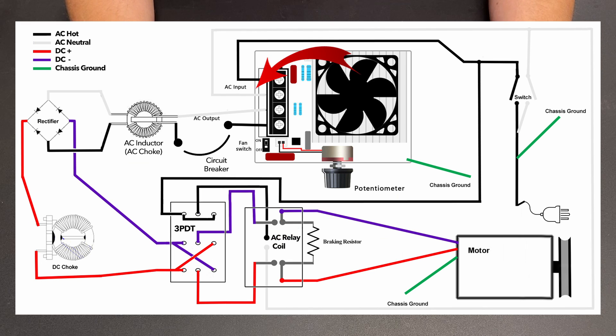The other leg of the T goes to the SCR voltage controller, and everything there is the same as other SCR hookups. So it's going to go through the circuit breaker, the AC inductor, the rectifier, the DC choke, and then we're going to go to our triple pole double throw switch.